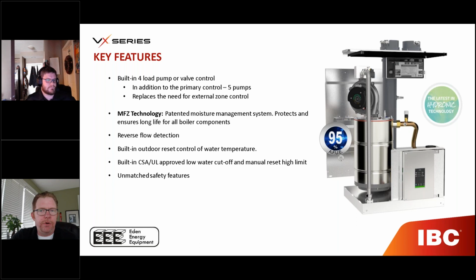It has reverse flow detection, built-in outdoor reset control, and as mentioned earlier, a built-in CSA and UL approved low water cutoff. So as far as safety features go, all the safety features you would expect from a boiler are built into this unit, which is nice.